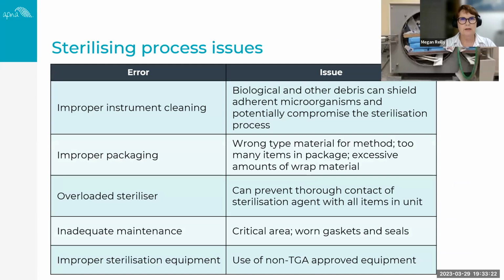So there are a number of sterilizing process issues that can actually occur, and I'm hoping your sterilizer up on the top right-hand slide never ever looks like this. Some of the common errors are initial improper instrument cleaning, and you can finish up with bioburden and other debris on the instruments, and that will impair the sterilization process. In actual fact, the microorganisms may become even more adherent to the surface of that device.